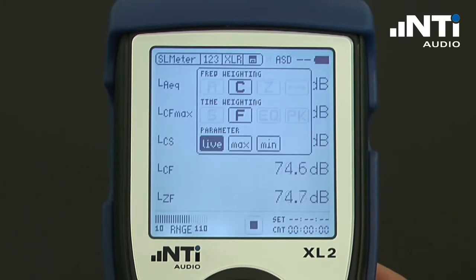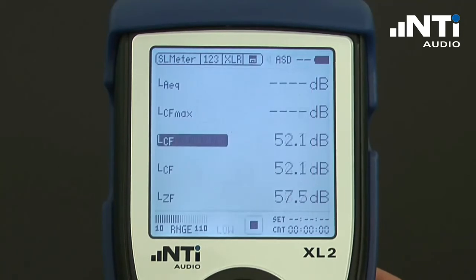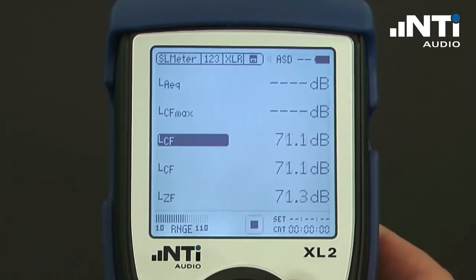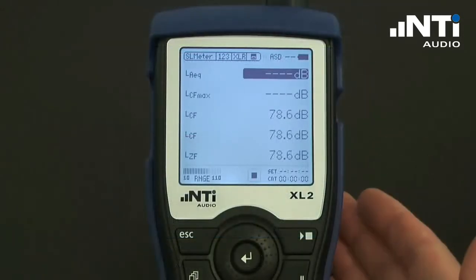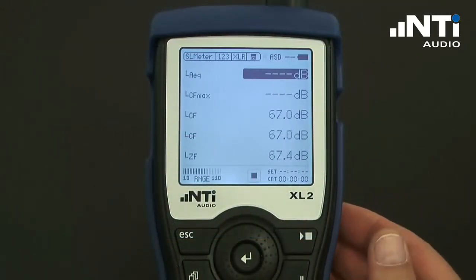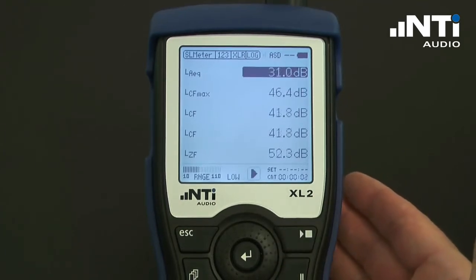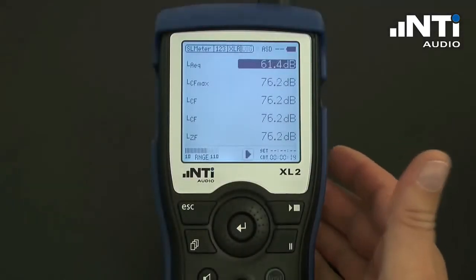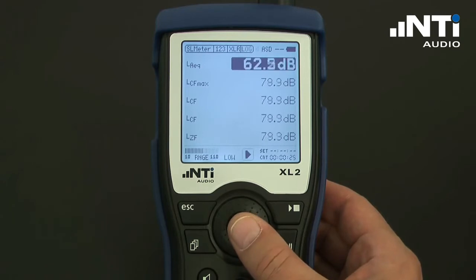Finally, we define whether we want to see live, minimum, or maximum values. Under any conditions, the XL2 measures all values in parallel. The user can choose which results he wants to have added to his screen and at what size. The size of the measurement results can be altered by pressing enter on the measurement value — it toggles between normal, bold, and x-large characters.